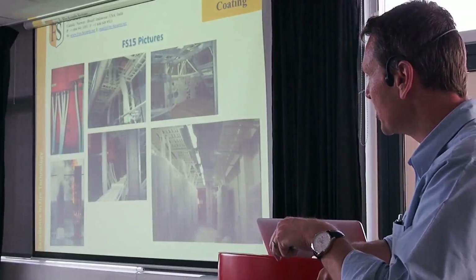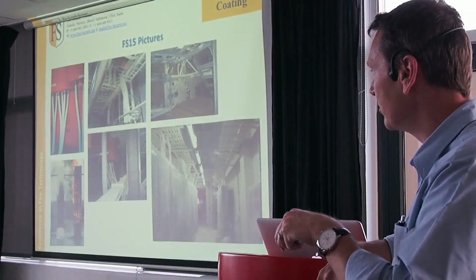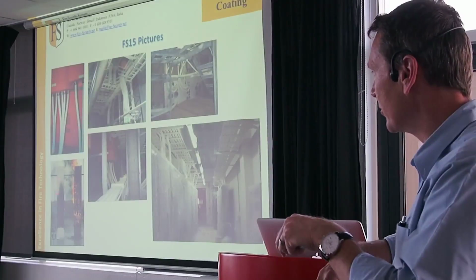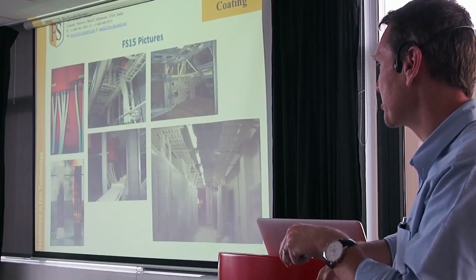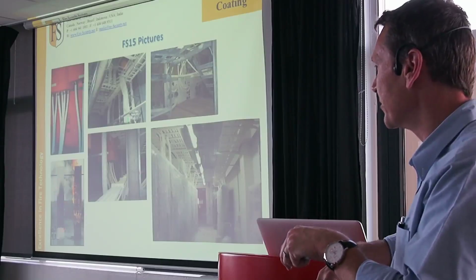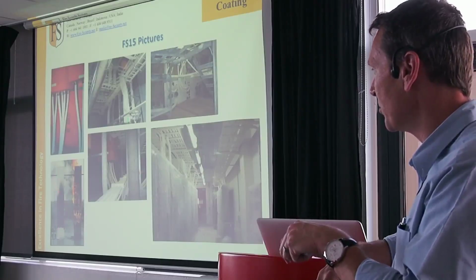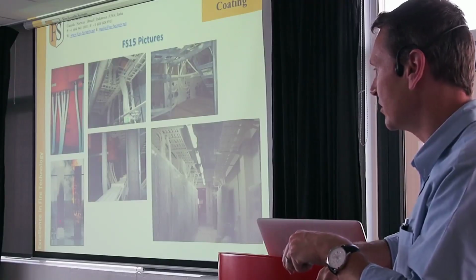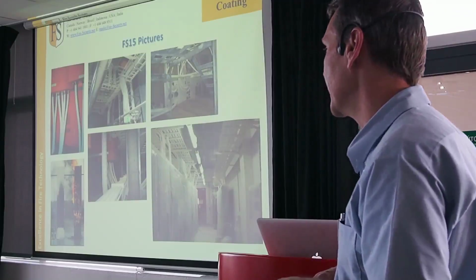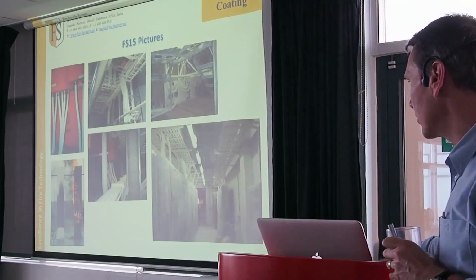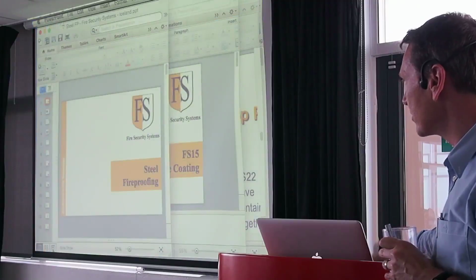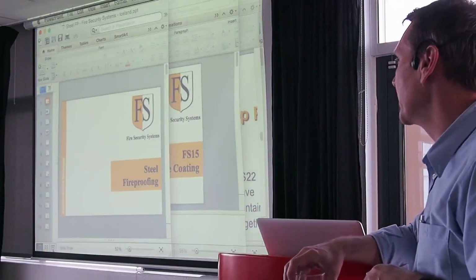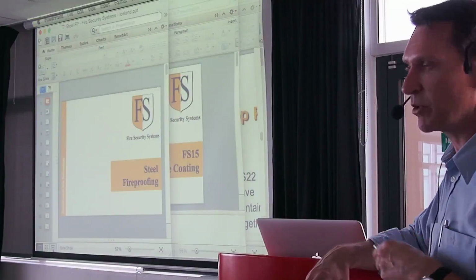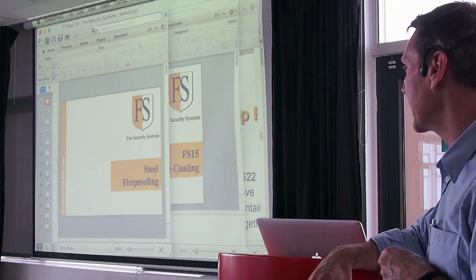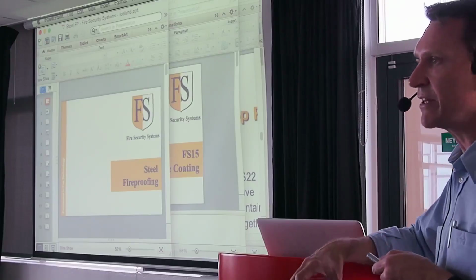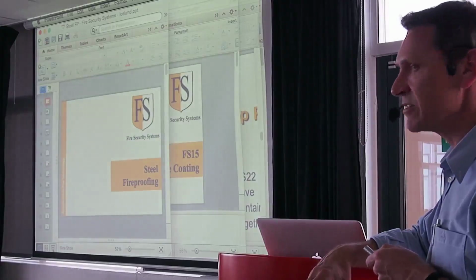And you'll see here, typical non-coated cable on fire, and the cable-coated cable here with zero flame spread. That's black because of the smoke. So what you can do is just get a wet rag and rub all of that smoke damage off the cable coating. You don't need to cable coat it again; it's fine. So it goes to show you that with a lot of methods with fire protection, with fire stopping, and we'll get to fire stopping in a minute, unless you want to break for 5 minutes. Cable coating is definitely the answer for zero flame spread and to save the facilities.